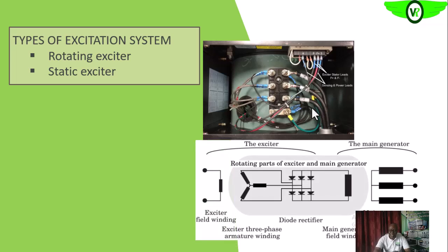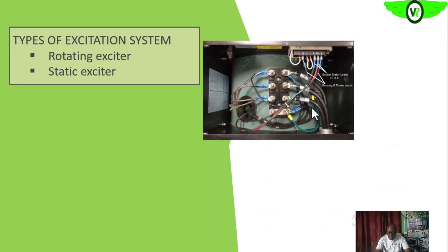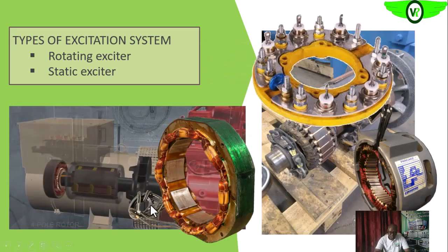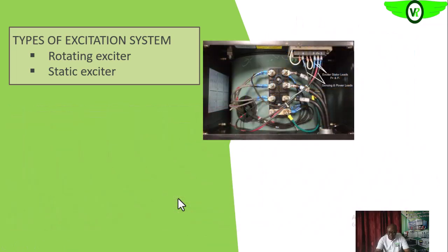As we said earlier, the field winding has some wires, and it has to be fed with DC. That DC voltage comes from an AVR like this. The positive and negative ends of the AVR, F minus and F plus, are fed to the exciter field: F plus to the positive end and F minus to the negative end of the exciter field.